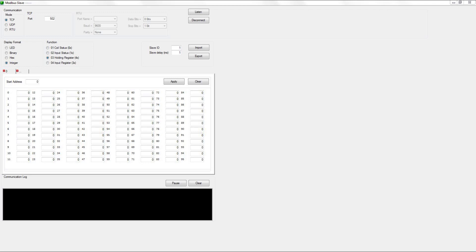There are four functions, every one is defined by a number. Three is read holding register, four is read input register, five is write single coil, and six is write single holding register. In TIA Portal they are numbered slightly different — see the help file. Alright, let's start.